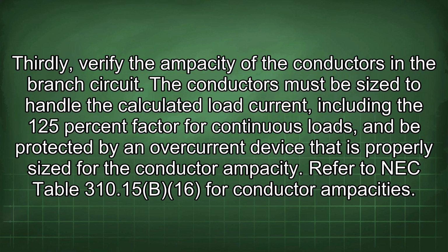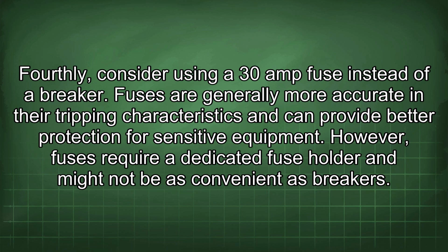Thirdly, verify the ampacity of the conductors in the branch circuit. The conductors must be sized to handle the calculated load current, including the 125% factor for continuous loads, and be protected by an overcurrent device that is properly sized for the conductor ampacity. Refer to NEC Table 310.15(B)(16) for conductor ampacities. Fourthly, consider using a 30 amp fuse instead of a breaker. Fuses are generally more accurate in their tripping characteristics and can provide better protection for sensitive equipment. However, fuses require a dedicated fuse holder and might not be as convenient as breakers.